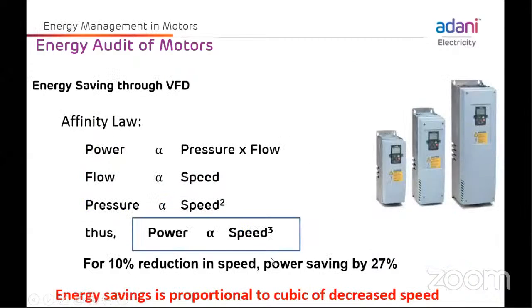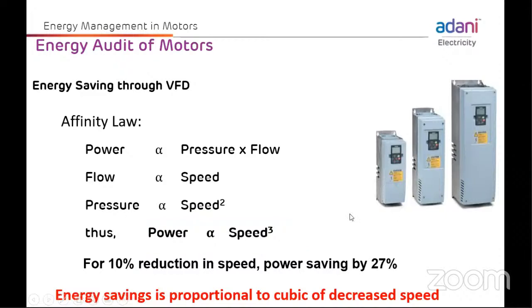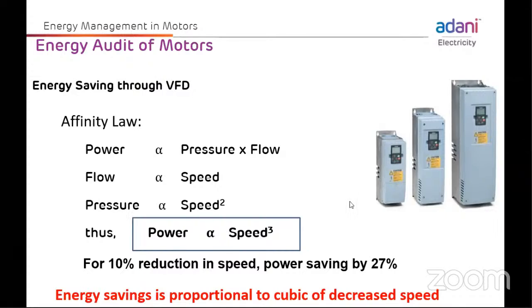Next, energy saving through VFD. This is also a process where the requirement is less, but our motor is running more. So the flow is more than the process requirement, and for that we are putting a valve.